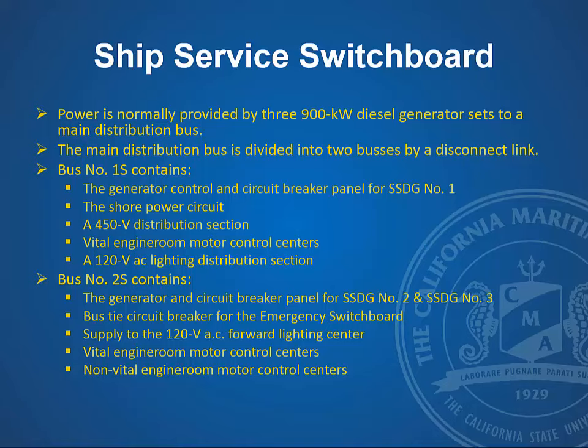So the power is normally provided by 3 900 kW diesel generator sets to the main distribution bus. The main distribution bus is divided into two, and there you have a disconnect link. This disconnect link would normally never be used unless there has been an emergency where the main switchboard has been damaged by a fire. Otherwise, this disconnect link is out of sight, out of mind. The only reason I bring it up is to make sure that you understand that these types of emergency services are provided and that you are looking for these types of things.